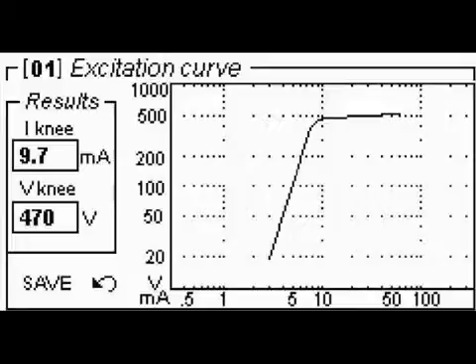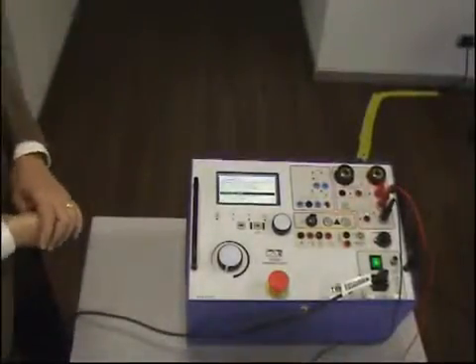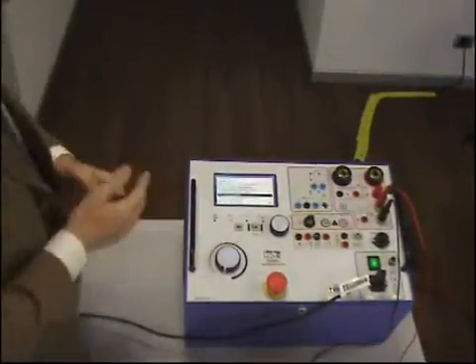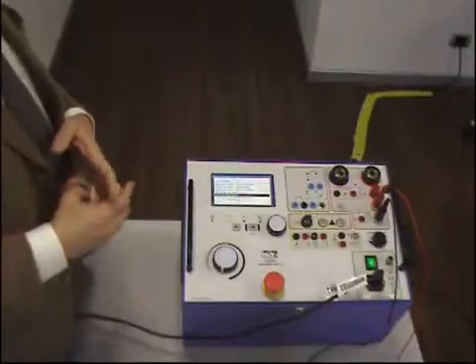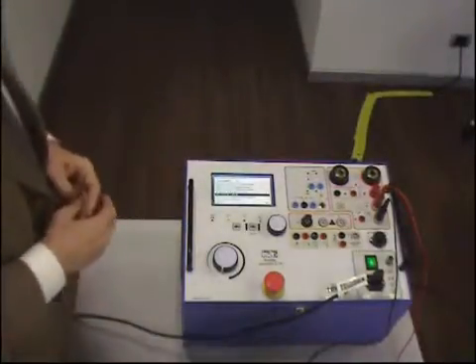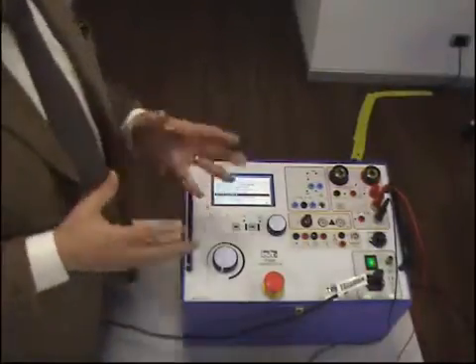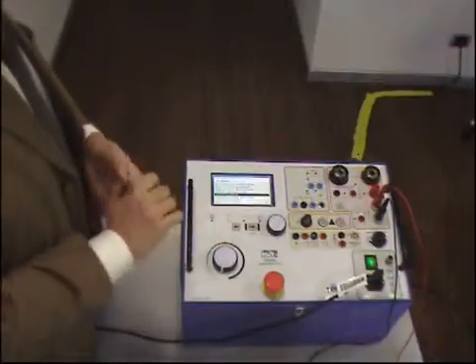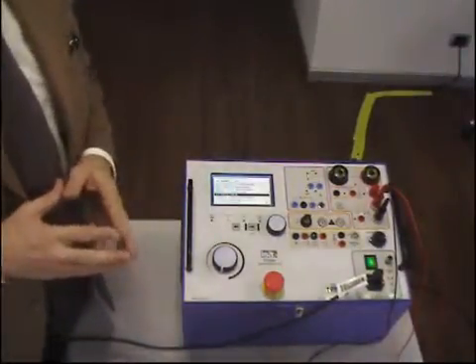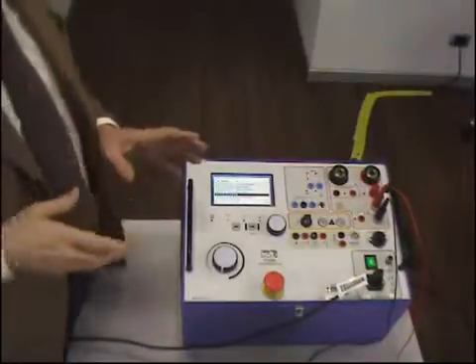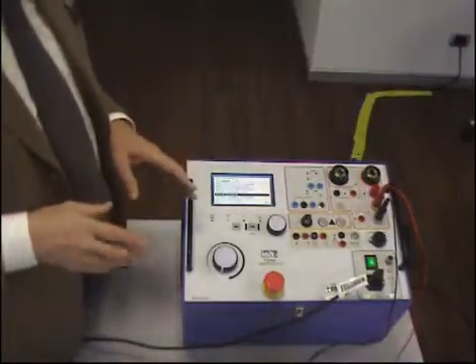Let's get started. The next and most interesting test is the excitation curve test, which allows you to verify the knee point of the current transformer. In this test, we apply a voltage to the secondary side of the current transformer, and increasing it will reach a moment when the current increases very much. There is an IEC definition of the knee point.